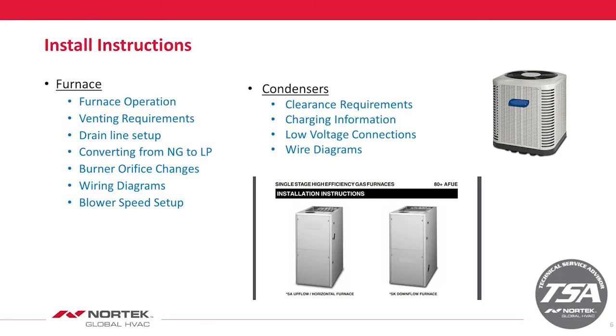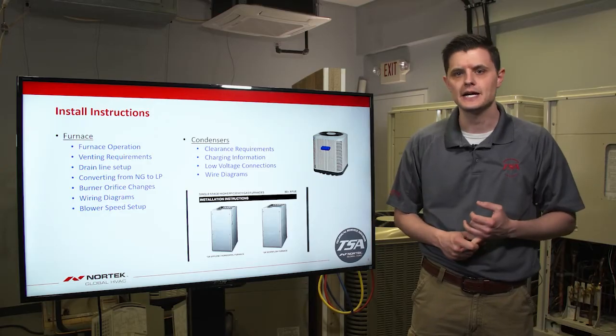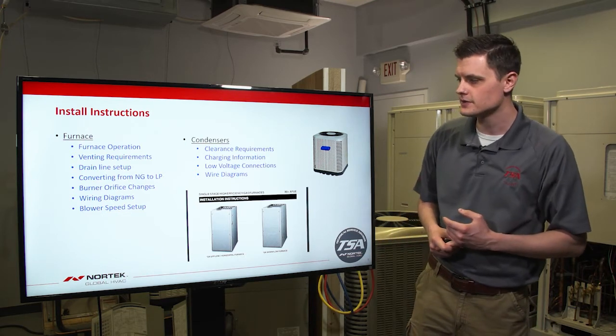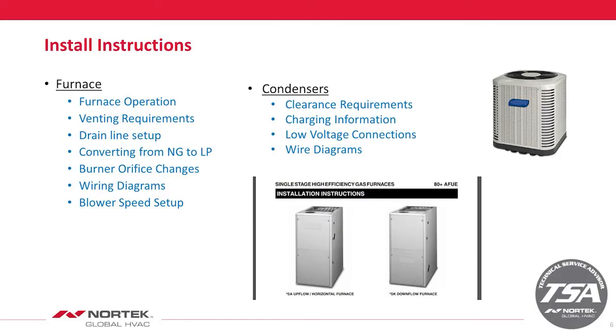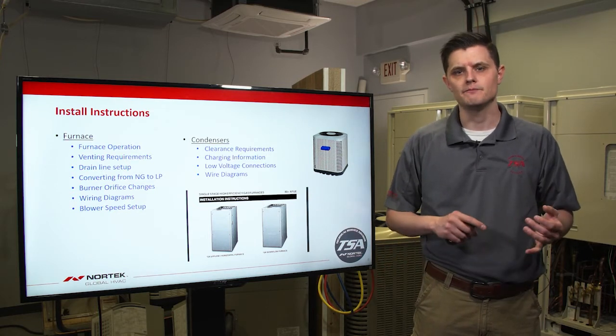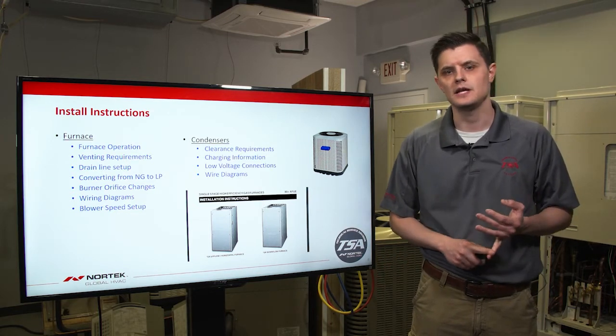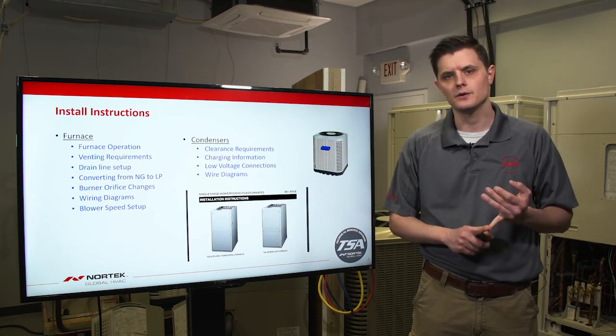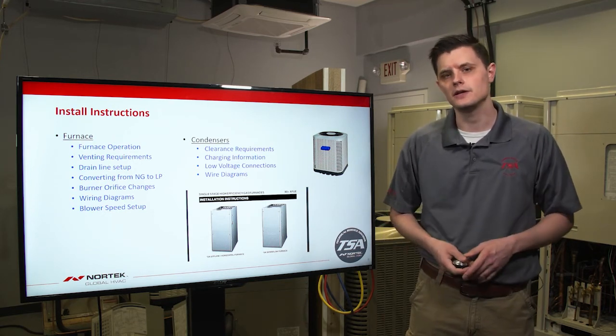On the condenser side, the install instructions will have clearance requirements. The main question we get is what the height requirement is for clearance when a condenser is being put under a deck—that can be found in your install instructions. We also include charging information, low voltage wire connections, and wiring diagrams on our condensers. If you're having questions on how to wire up a condenser on the low voltage side—especially for heat pumps and which wires go with which terminals—that can be found in our install instructions.